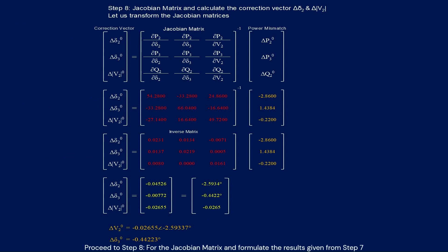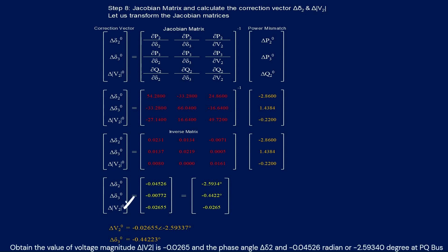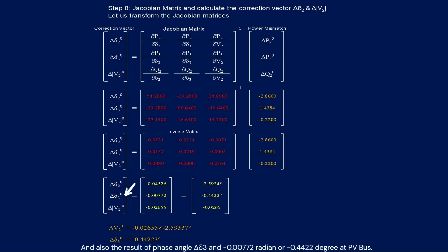Proceed to Step 8: formulate the Jacobian matrix from the results of Step 7. The correction vector equals the inverse of the Jacobian matrix multiplied by the power mismatch. Obtaining the values: voltage magnitude correction = −0.0265, phase angle correction = −0.04526 radians or −2.5934 degrees at the PQ bus, and phase angle correction = −0.00772 radians or −0.4422 degrees at the PV bus.